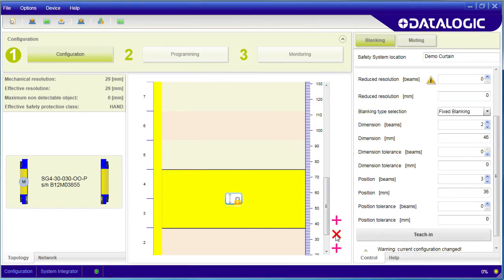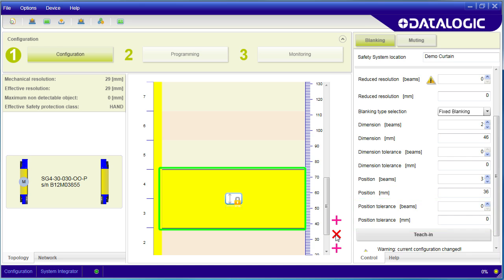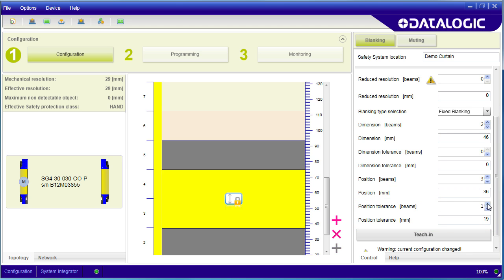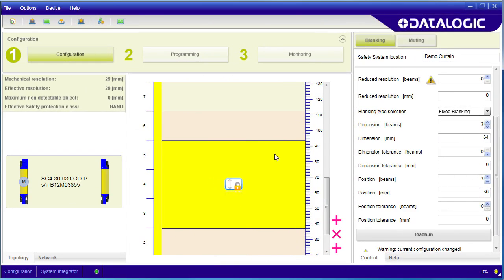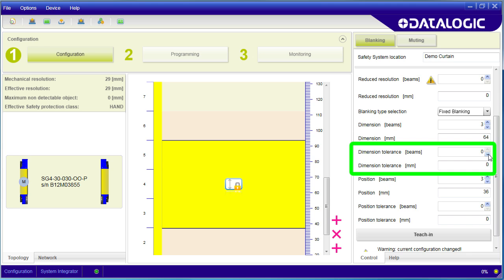You can also add a position tolerance. Maybe you know a machine part only blocks these two beams, but it moves around a bit due to vibration. This says this obstruction can move up or down one beam without setting off the outputs. Or maybe the blockage stays in one place, but it changes in size.